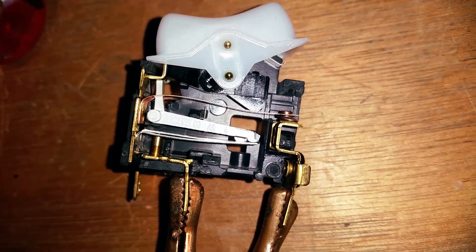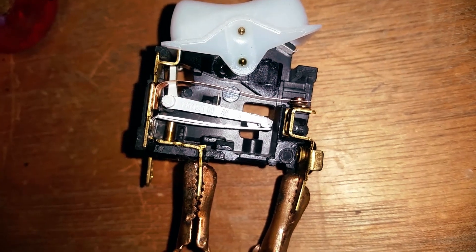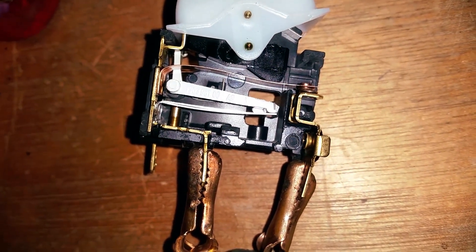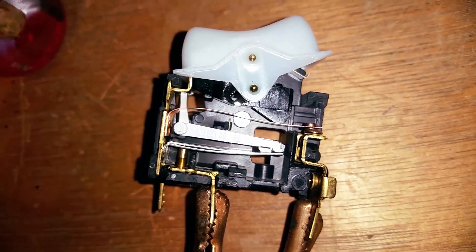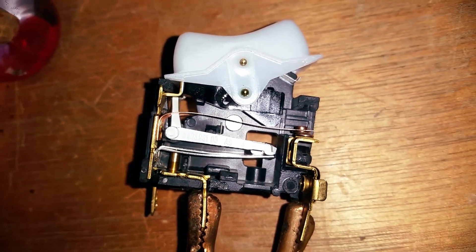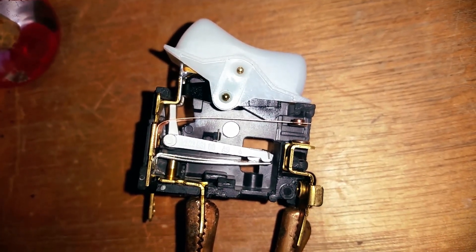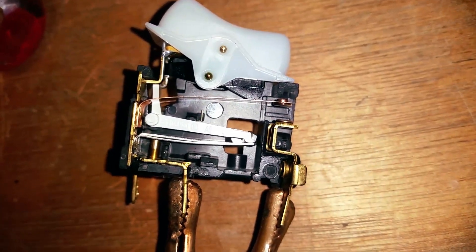These types of switches are often used as thermal circuit breakers in motors and other high-current electrical equipment. If the temperature exceeds a hazard limit, the switch opens and current is cut. As the equipment cools, the switch closes, restoring current.